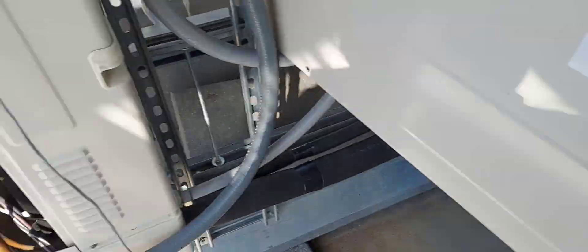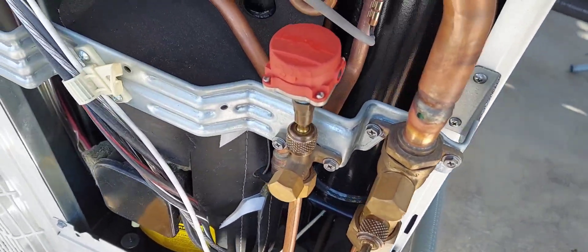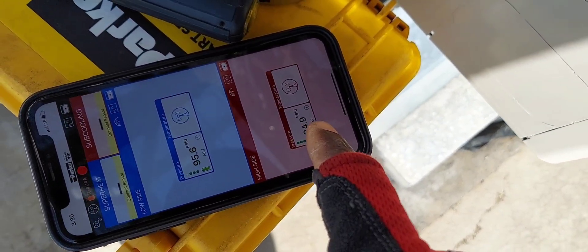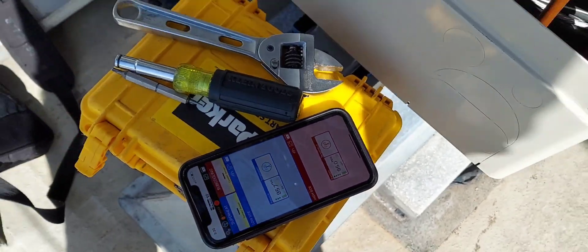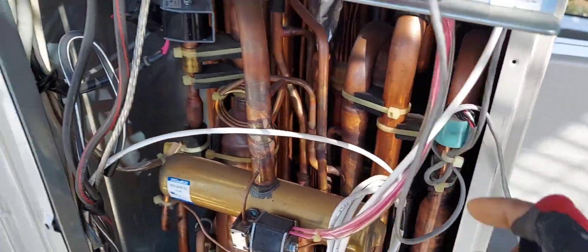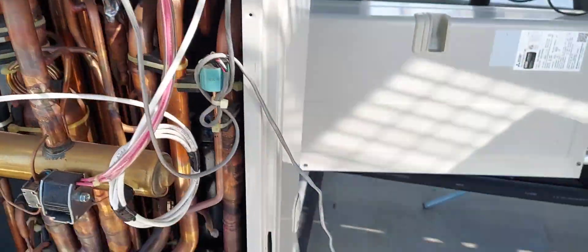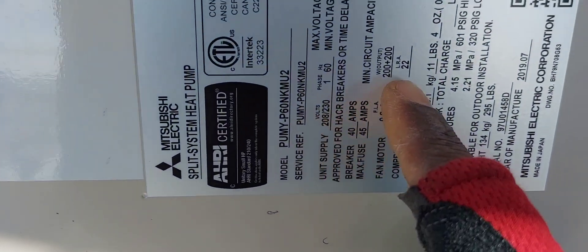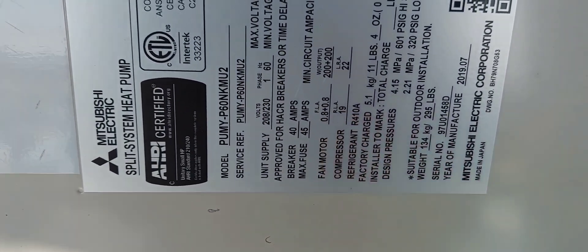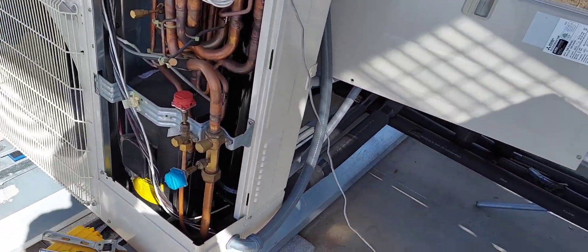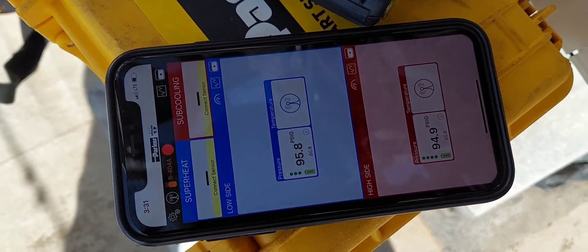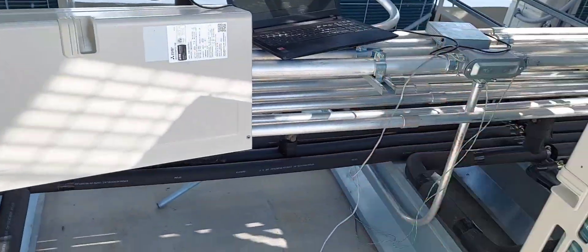Based on my Parker sensors — connected high side and low side — I'm reading 95 and 94 PSI standing, basically identical. That tells me pressure transducer trouble or not. Here's your low-side pressure transducer and that's the high side right there. This is an R-410A system, and standing at 95 PSI, by the time this compressor turns on we're going to be in low pressure already. By the time the compressor turns on this is going to hit 75 right away — we have a refrigerant charge problem right here.